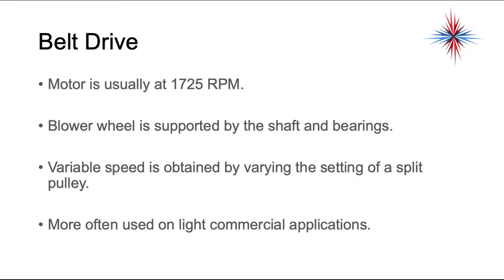The other type of blower assembly is called a belt drive. The motor is usually 1725 RPM. The blower wheel is supported by the shaft and bearings. Variable speed is obtained by varying the settings of a split pulley — in other words, how tight the belt is. It's more often used in commercial applications; you don't see a lot of these in residential.